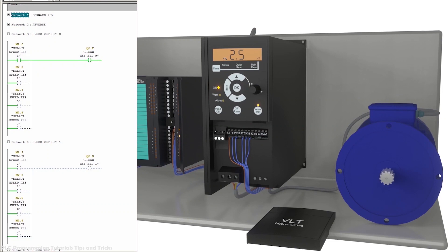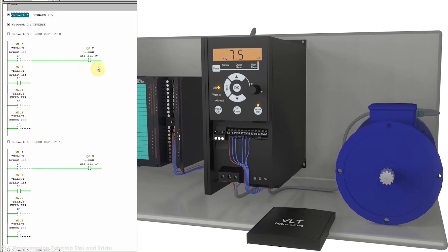Next we turn on M2.1 (select speed reference 2), which turns on Q0.3 (speed reference bit 1) and the VFD loads preset frequency reference 2 — 2.5 Hz. The motor starts running at 2.5 Hz. Next, turning on M2.2 (select speed reference 3) activates Q0.3 and Q0.2 — bit 1 and bit 0 — whose sum is 3, so the VFD loads preset frequency reference 3 — 7.5 Hz.